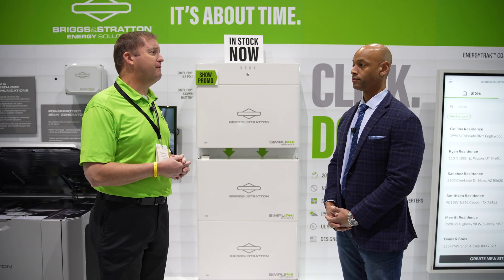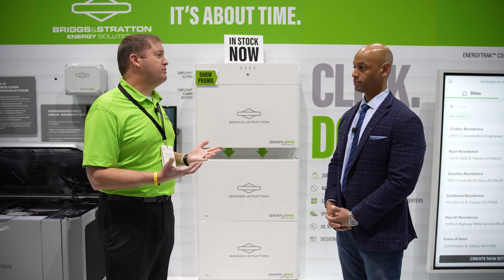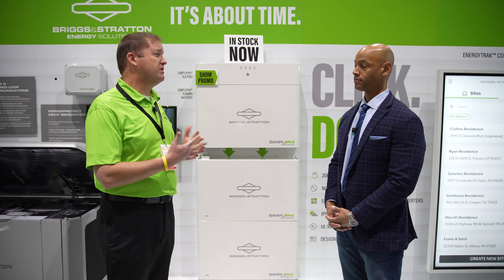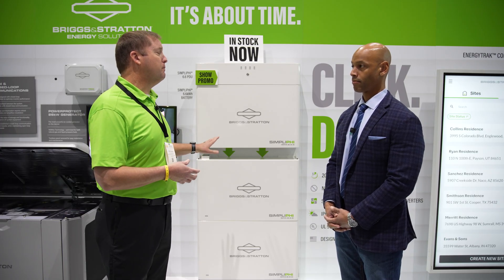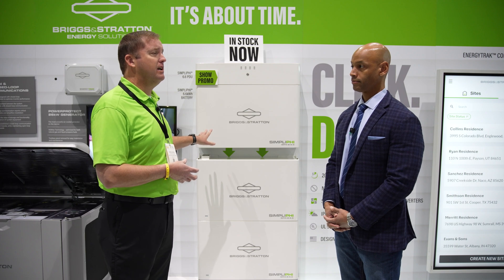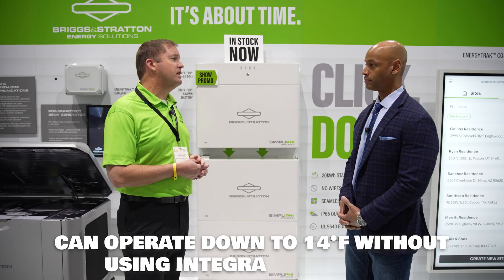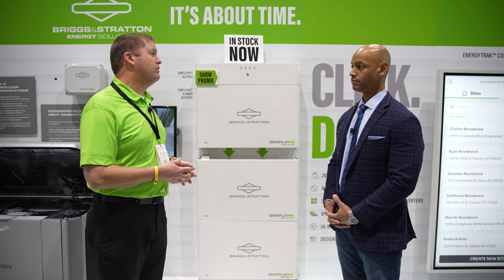We know lithium-iron phosphate chemistries have a hard time in cold weather. We can do heaters, but they do use up energy to heat. So what we've done is optimize some of the electrolyte in the cell structure so we can operate down to 14 degrees Fahrenheit and still not need to use heaters in those applications. Absolutely, we can put these indoors or outdoors.